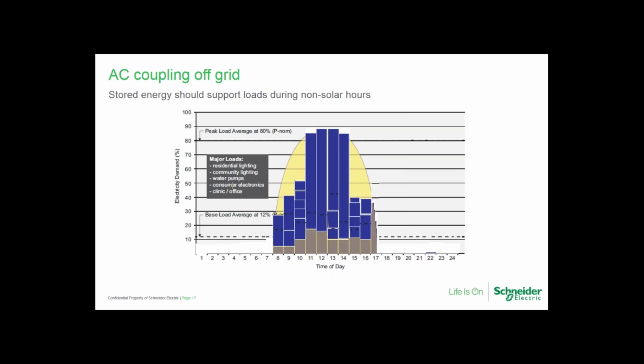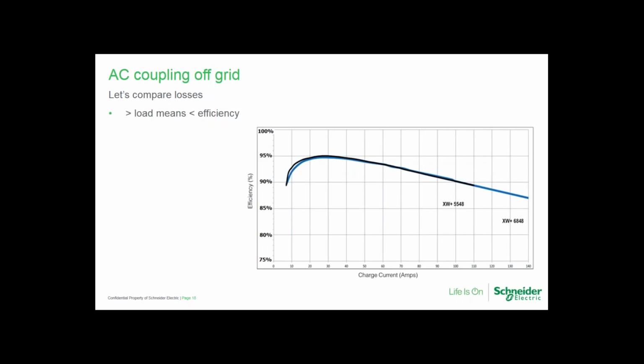Here we can see the efficiency graph for the XW charging. You're up around 95% when you're at around 3 kW. At 4 kW it starts to drop off, or actually 30% of total. And when you get up to around 100% of the output capacity of the XW, you're going to get around 90% efficiency.